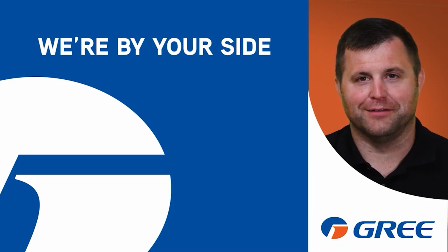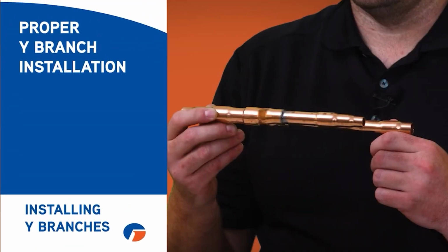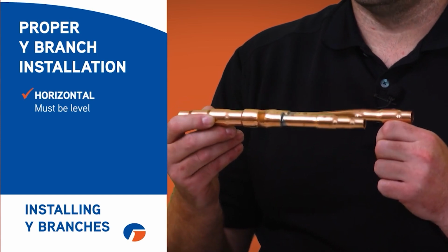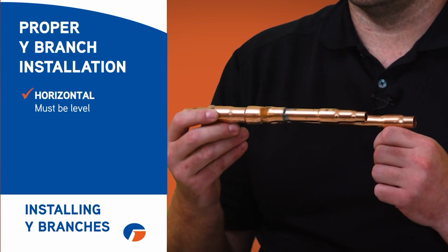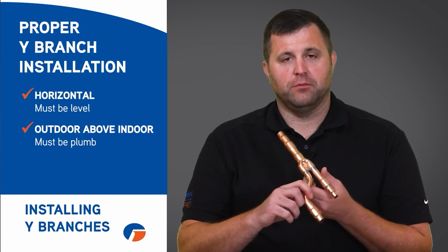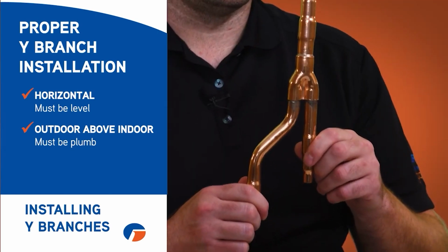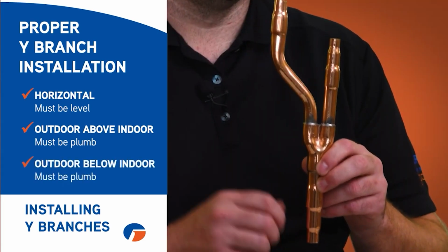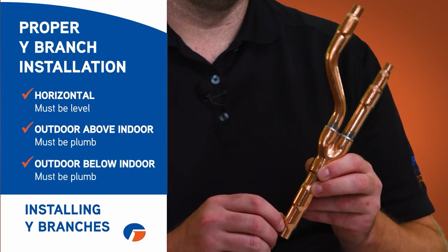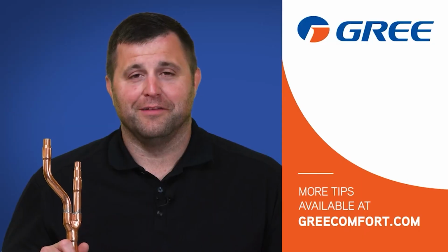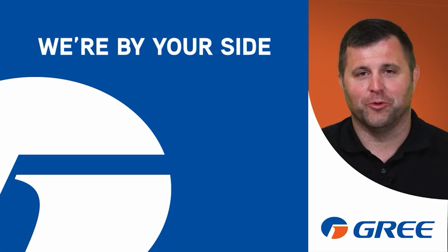At GREE, we're by your side. Hi, I'm James McIntyre from GREE with an installation tip for MultiPRO. When installing Y branches, there are 3 ways that they can be installed for them to be installed properly. One, if they're horizontal, they must be level. If they're leaning one way or the other, it can absolutely affect the performance of the system. If the outdoor unit is installed higher than the indoor units, the Y branch can be installed this way, but it must be plumb, or straight up and down. If the outdoor unit is below the indoor units, it can be installed this way, but it must be plumb, otherwise known as straight up and down. If they are leaning, it will affect performance of the system. And that's why it's a good idea to have a level on the job site. At GREE, we're by your side.